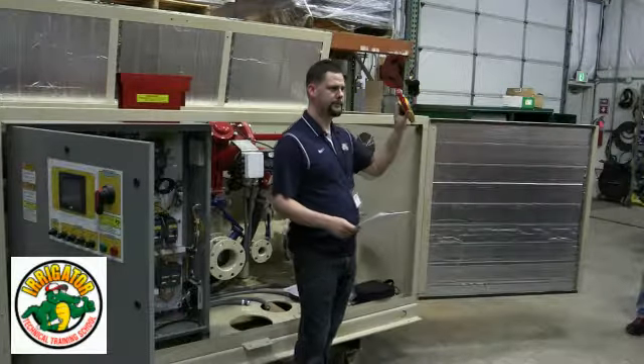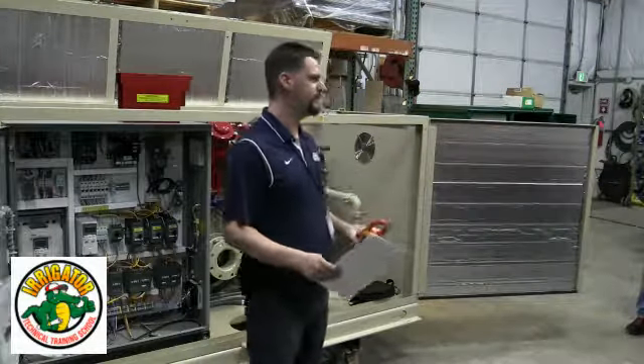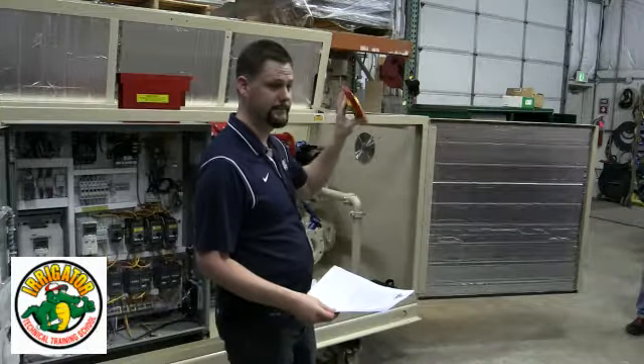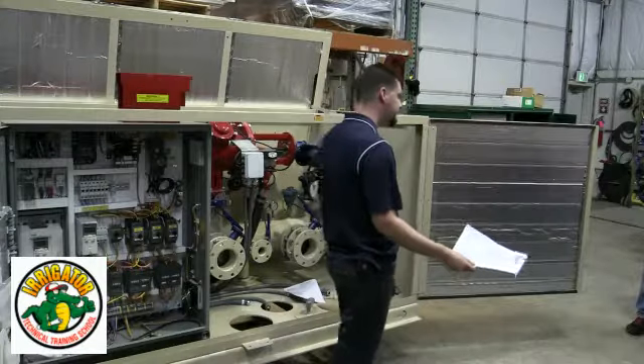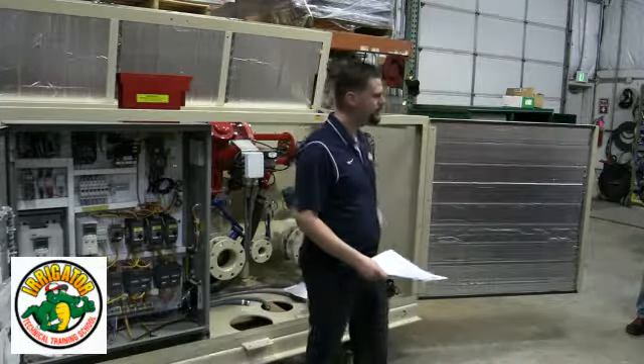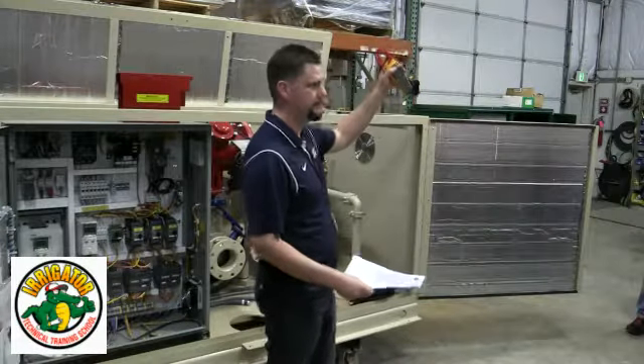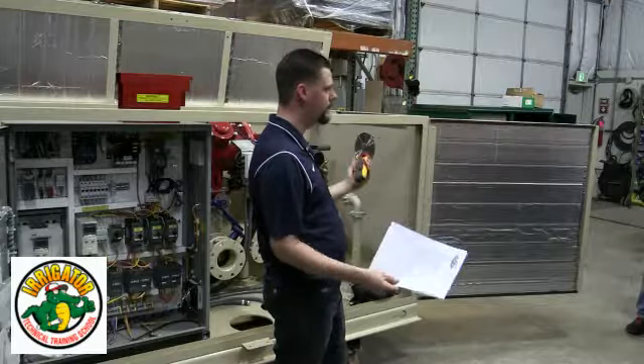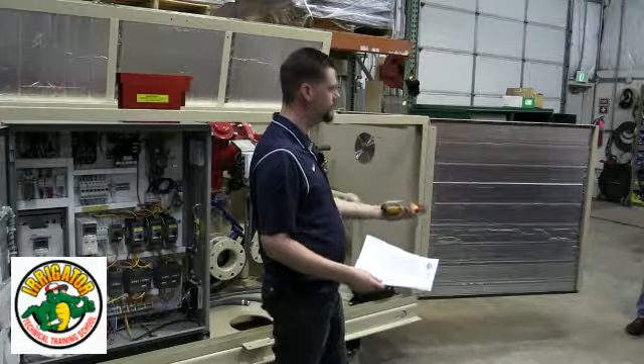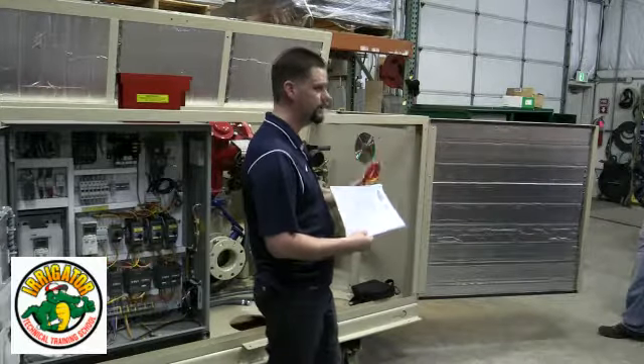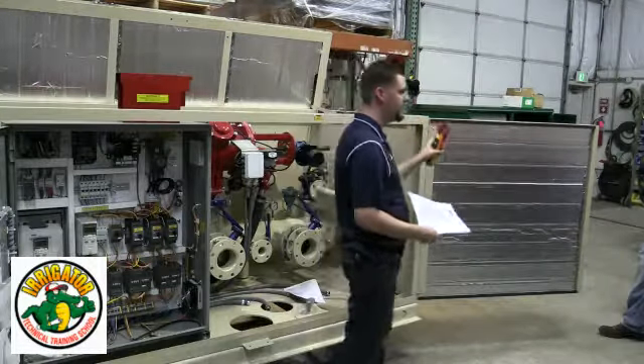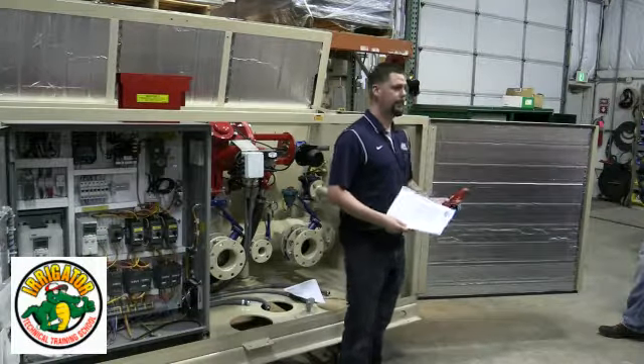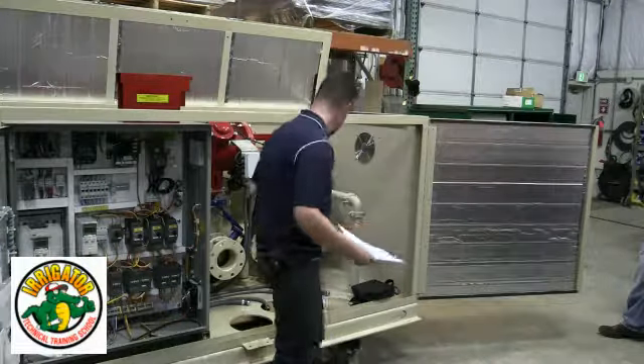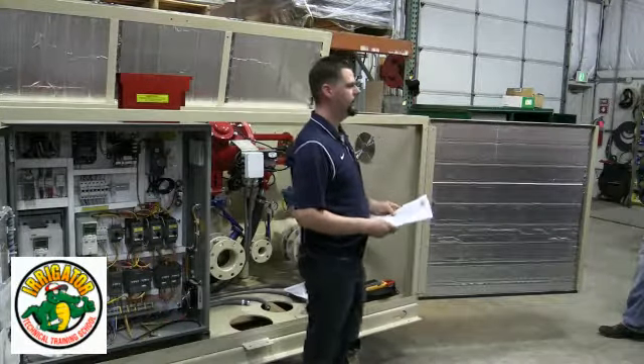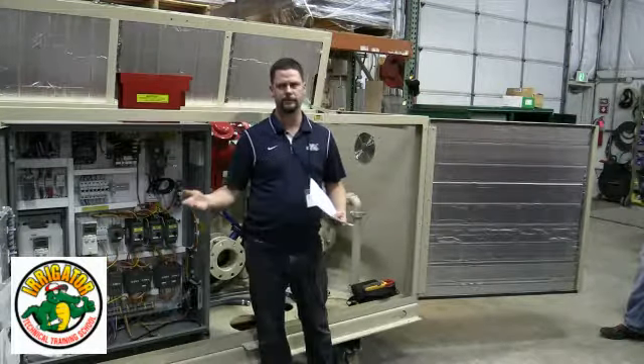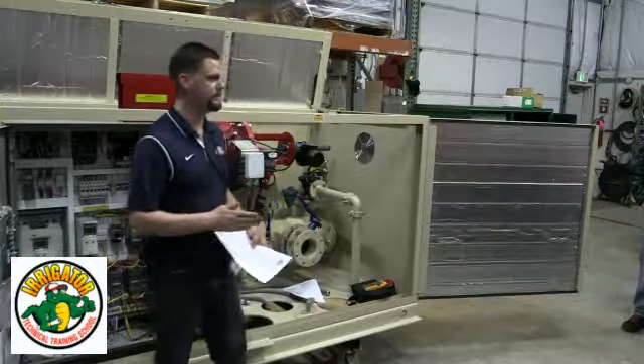But the amp meter. If you get ambitious, and I don't expect everyone to do this, this is one of those qualified personnel deals. Not everyone has an amp meter, I understand. But if you have one, it's a good idea to put it on each motor lead while it's running full speed. Otherwise, it'll be less, and you won't know why. Full speed. 1, 2, 3. They should all be pretty close. Now, if you've got one that's 10 and one that's 30 and one that's 2, you should be tripping a breaker. So if you have the ability to do that, I would recommend you do each motor by itself while it's running full speed.